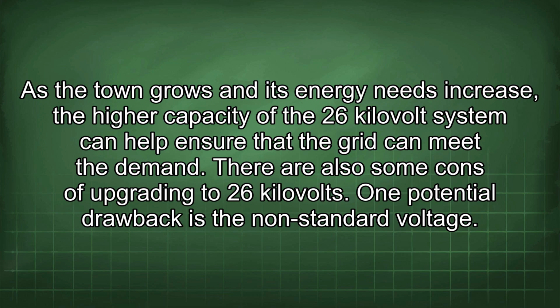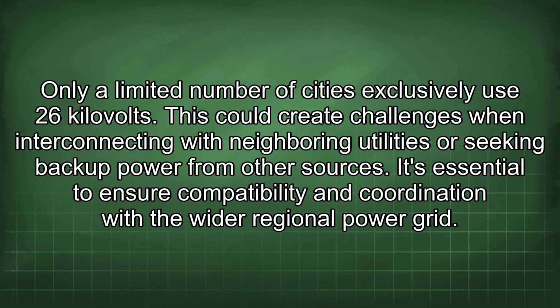There are also some cons of upgrading to 26 kilovolts. One potential drawback is the non-standard voltage. Only a limited number of cities exclusively use 26 kilovolts. This could create challenges when interconnecting with neighboring utilities or seeking backup power from other sources. It's essential to ensure compatibility and coordination with the wider regional power grid.